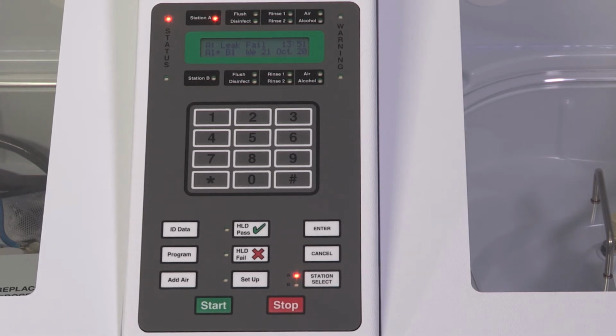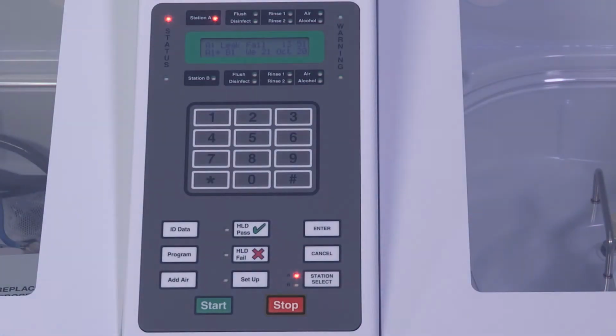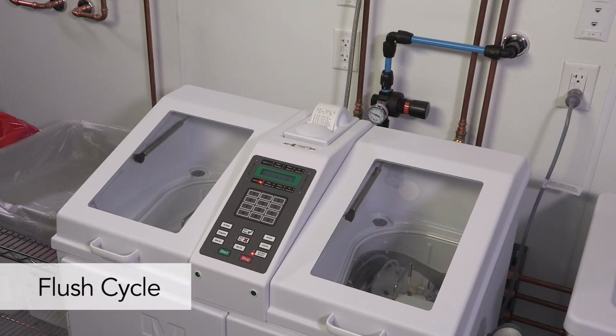At the end of the cycle, the control panel's warning LED indicator lights blink, and a leak fail error message displays on the screen. On the control panel, press Stop to acknowledge and clear the warning message. Troubleshoot using the same methods described for a major leak. Restart the cycle. If a minor leak is still detected, remove the endoscope from the basin and from service. An endoscope that has a failed leak test cannot be used in a patient procedure and must be sent out for repair. Next, the flush cycle begins.